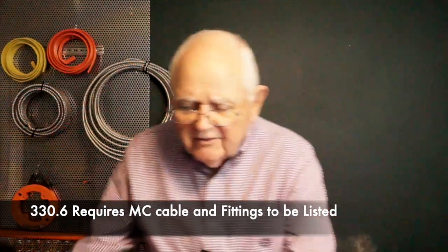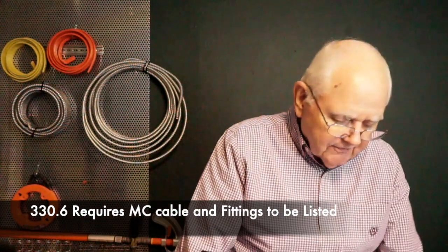It tells me that everything has to be listed and identified for use when it comes to MC cable. So we are using the 2020 version of the NEC, as always, the latest version. And 330.6 says type MC cable shall be listed. Fittings used for connecting type MC cable to boxes, cabinets, or other equipment shall be listed and identified for use.